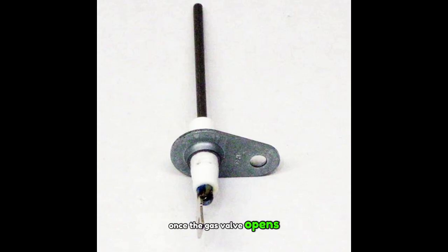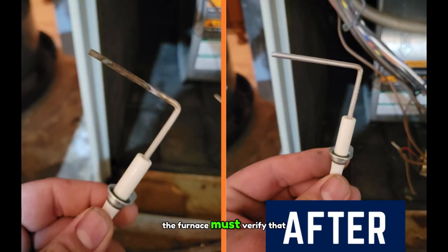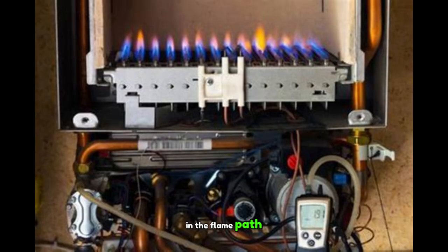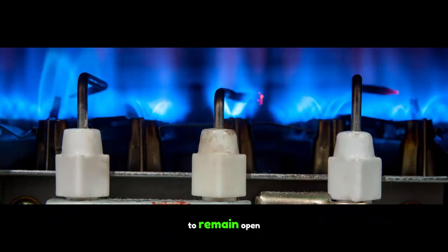Flame sensors, proof of ignition. Once the gas valve opens and the burners ignite, the furnace must verify that a flame exists. This is where the flame sensor comes in. It's a metal rod placed in the flame path. When it detects the presence of a flame, it allows the gas valve to remain open.